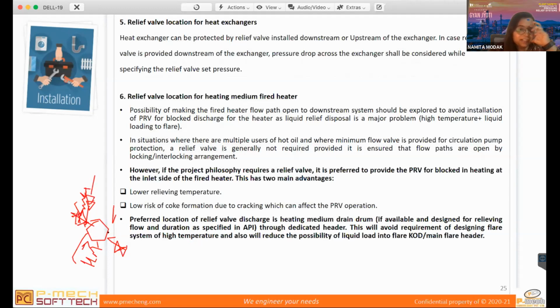There are some cases where your cold side and hot side, as per ASME, the 10/13 rule should be there. I mean, your higher design pressure, let's say it's 10 bar gauge, then your lower design pressure minimum should be 10/13 times of 10. So if you're designing by the 10/13 rule, then a PSV is not required for the heat exchanger.